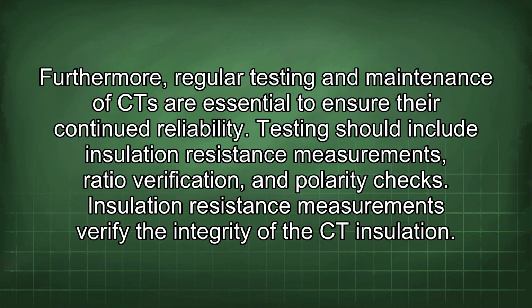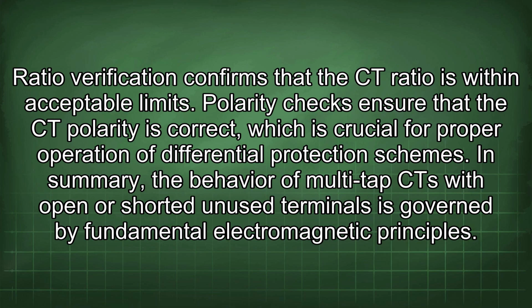Furthermore, regular testing and maintenance of CT are essential to ensure their continued reliability. Testing should include insulation resistance measurements, ratio verification, and polarity checks. Insulation resistance measurements verify the integrity of the CT insulation. Ratio verification confirms that the CT ratio is within acceptable limits. Polarity checks ensure that the CT polarity is correct, which is crucial for proper operation of differential protection schemes.